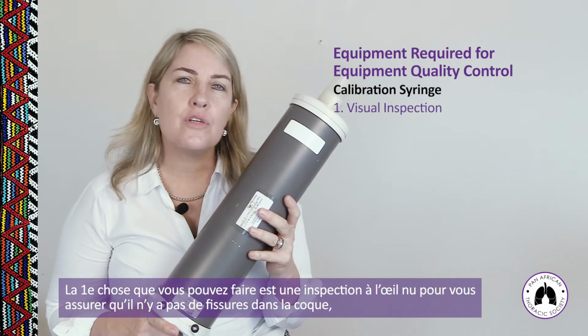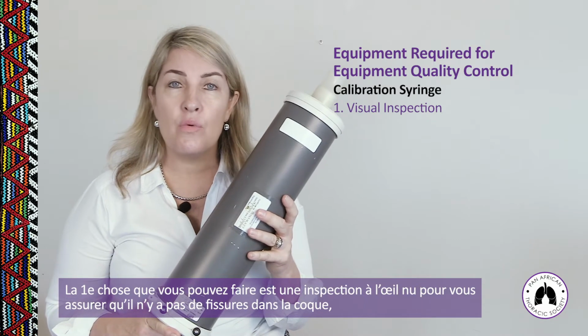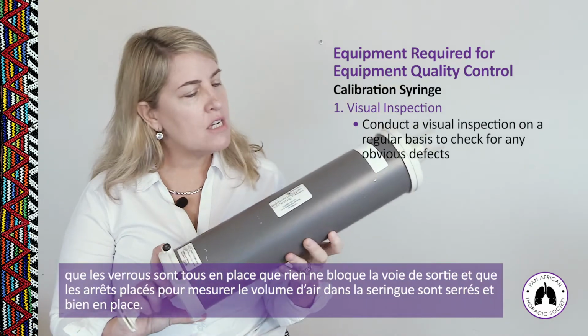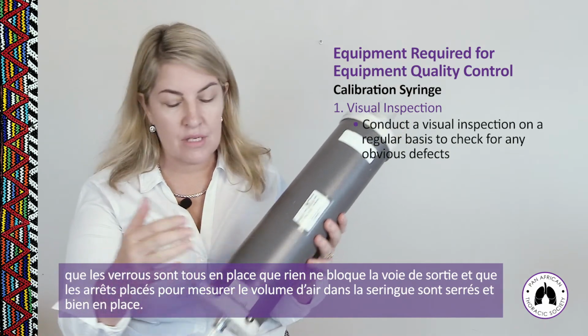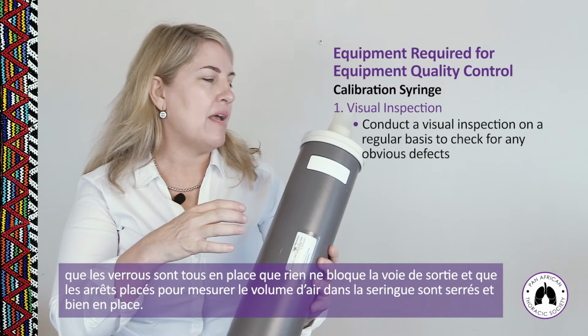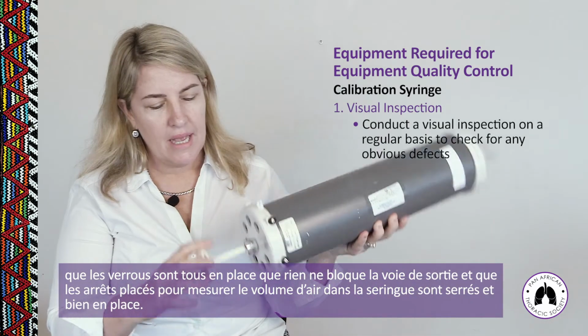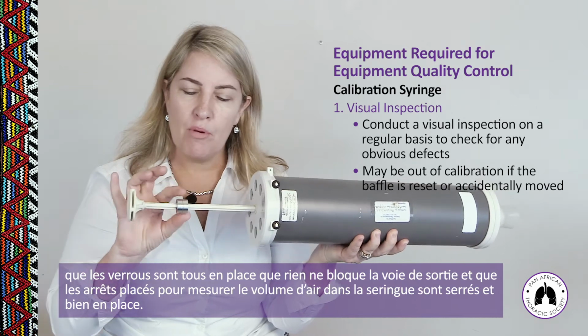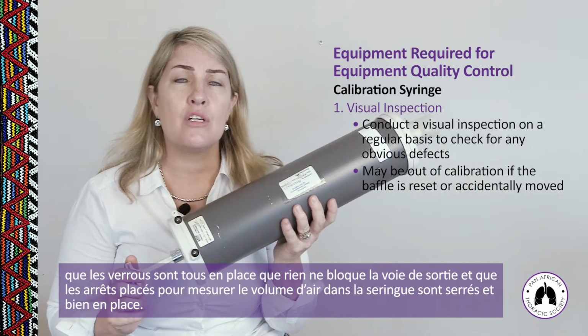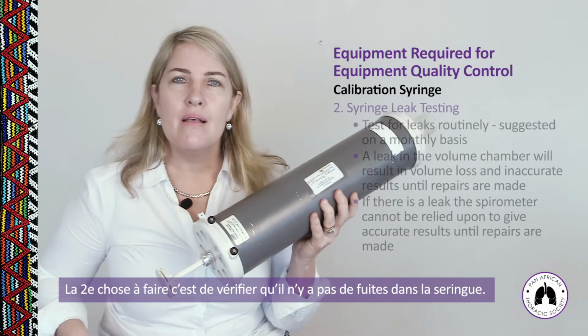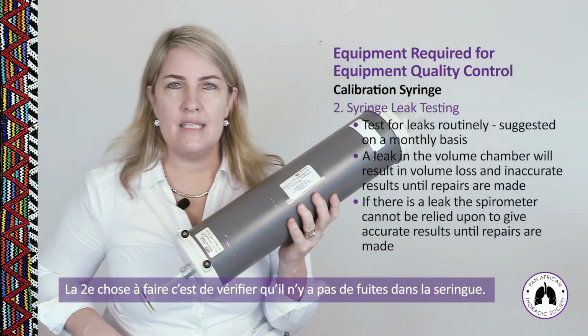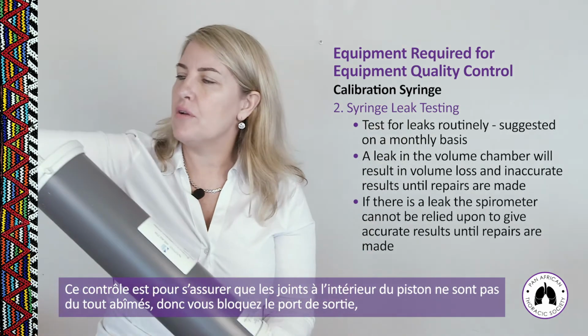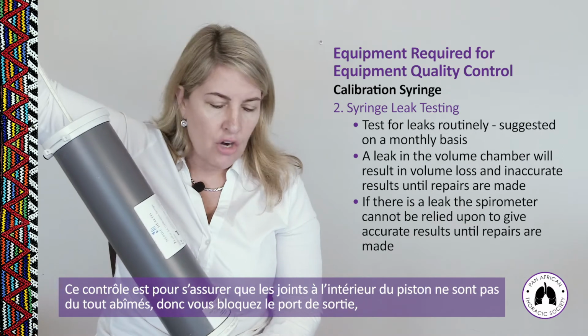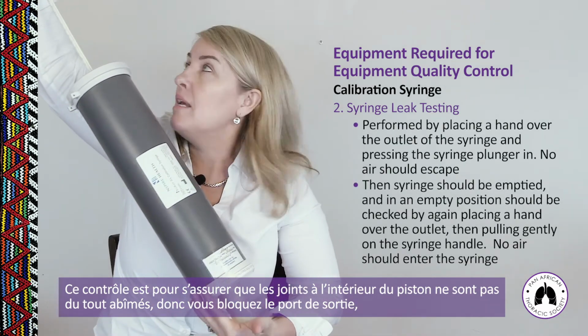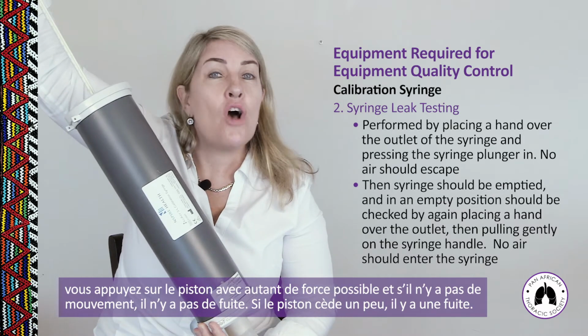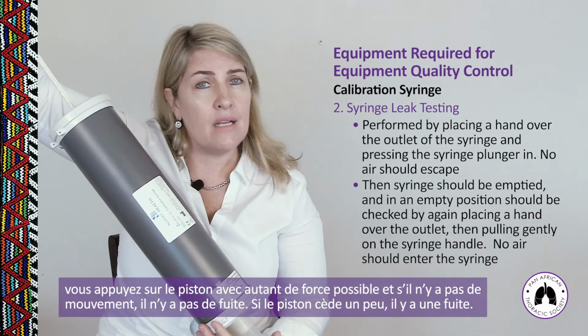So the first thing you would do to care for your syringe and understand that it's in good working order is to do a visual inspection. A visual inspection is just to make sure that there's no cracks in the housing, there's no lost screws, that there's nothing blocking the outlet port, and that the little baffles that actually are put in place to measure the volume of air in the syringe are tight and firm. The next thing you would do is a syringe leak test. And a syringe leak test is really making sure that the seals inside the plunger are not broken in any way. So you would occlude the outlet port, push down on your handle as hard as you can, and if there's no give, there's no leak.